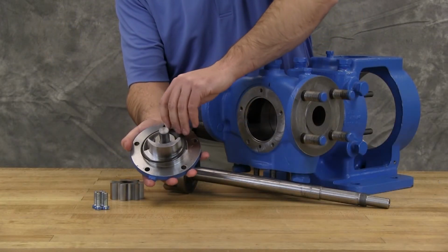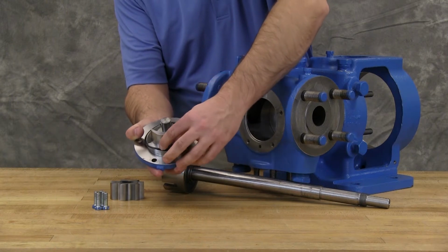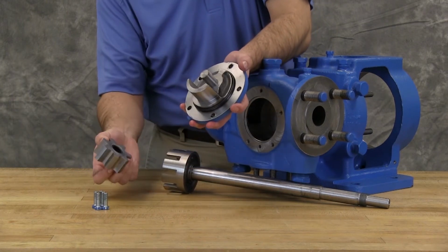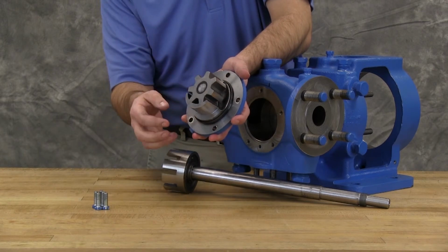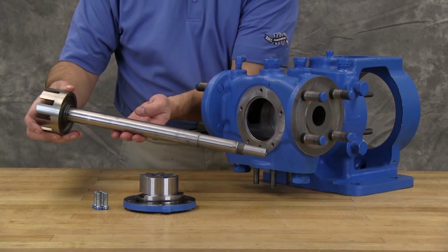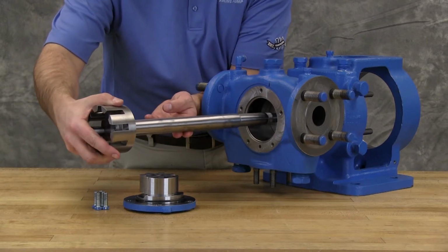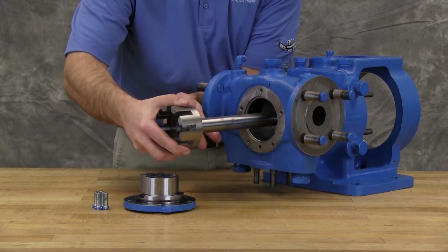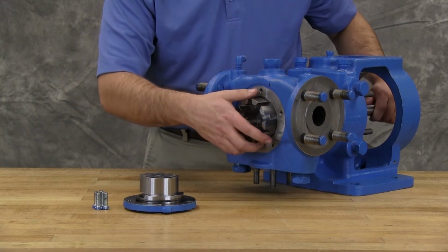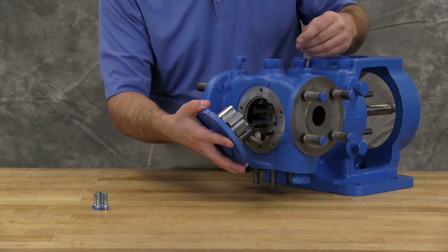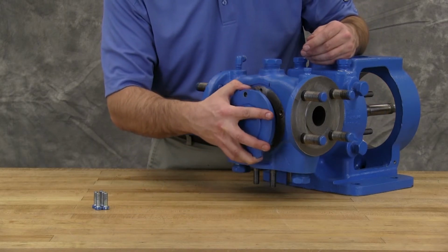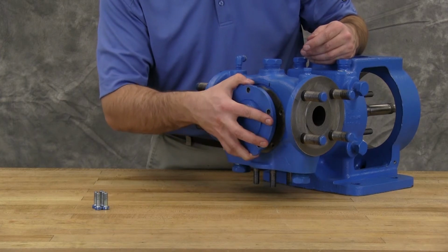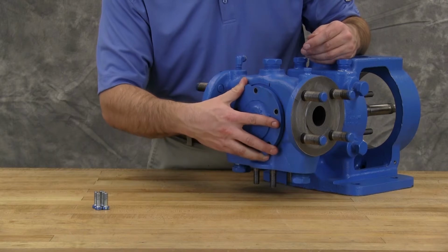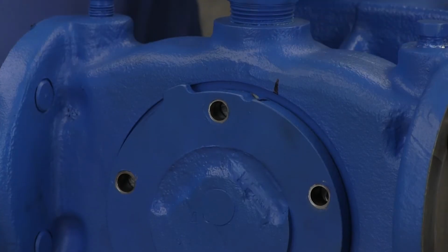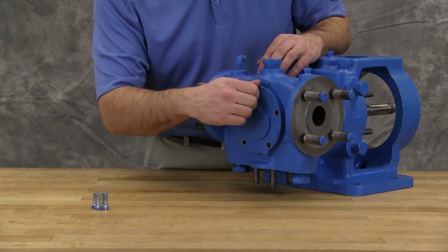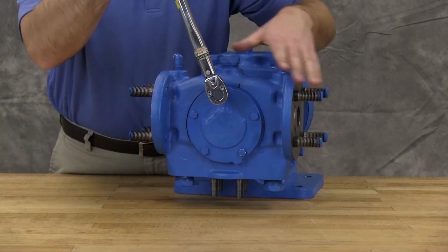Place the O-ring on the head. Coat the idler pin with light oil and install the idler onto the pin on the head. Lubricate the shaft and inner diameter of the shaft bushing. Slide the shaft assembly and rotor into the casing. Reinstall the head and idler gear. The aligning marks that were made during disassembly ensure the proper location of the pin and crescent. Tighten the head cap screws evenly per TR 804 cap screw torques.